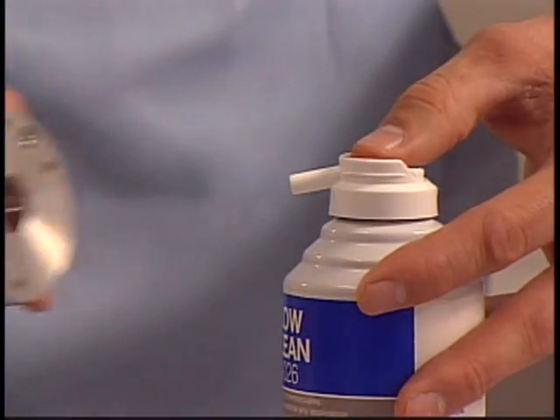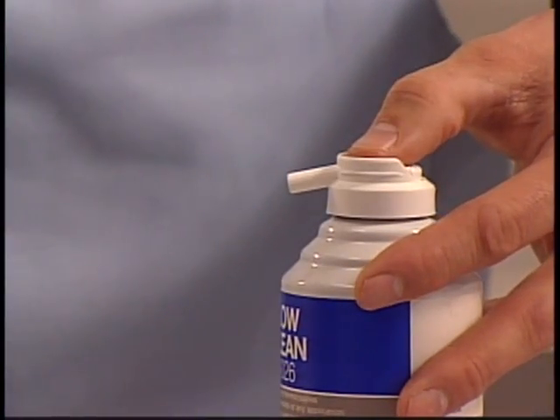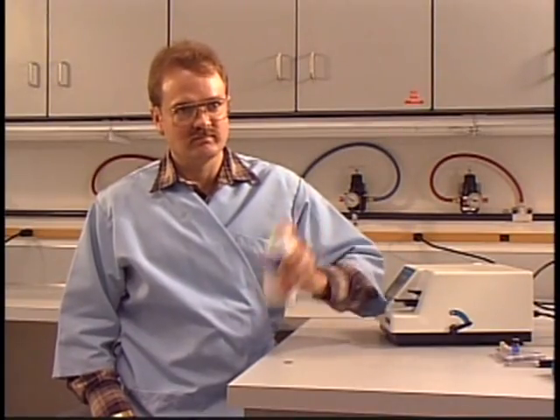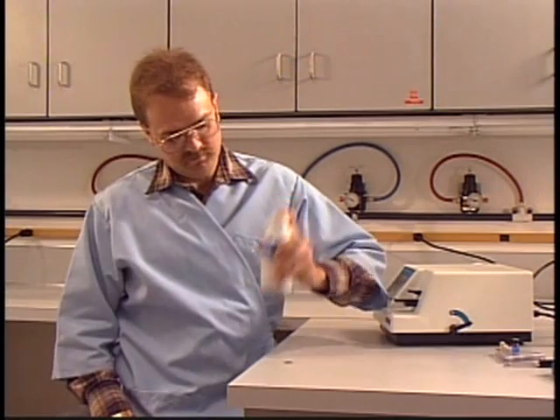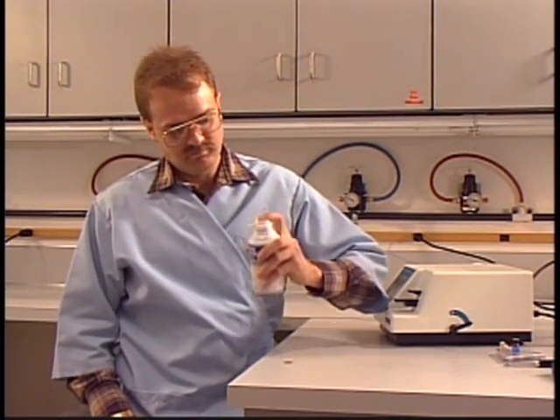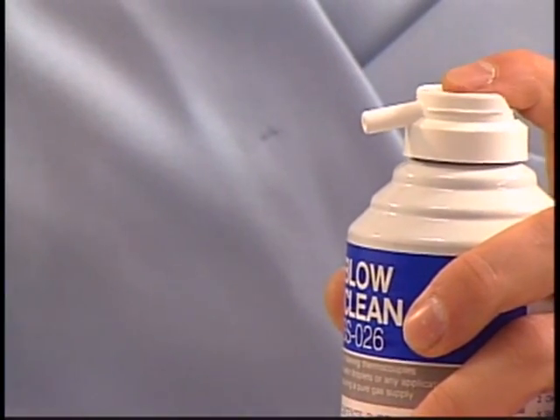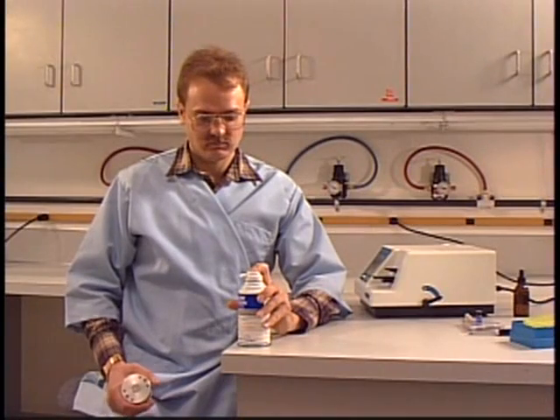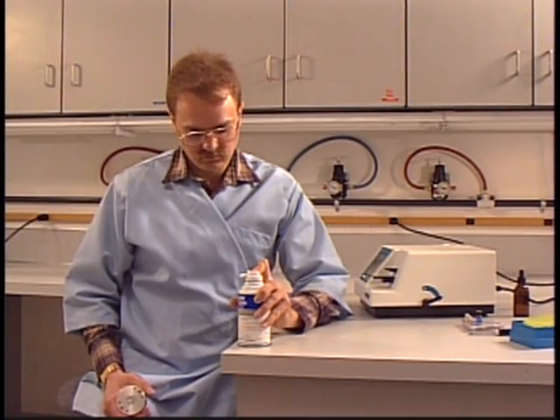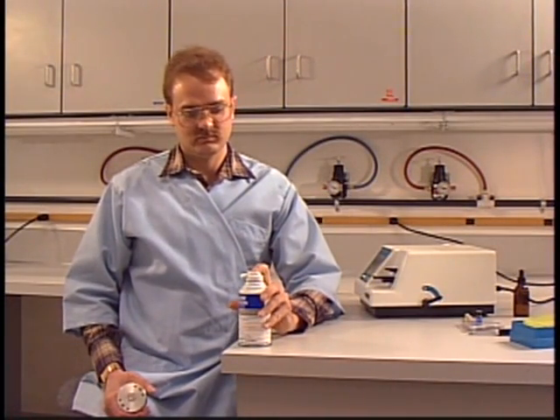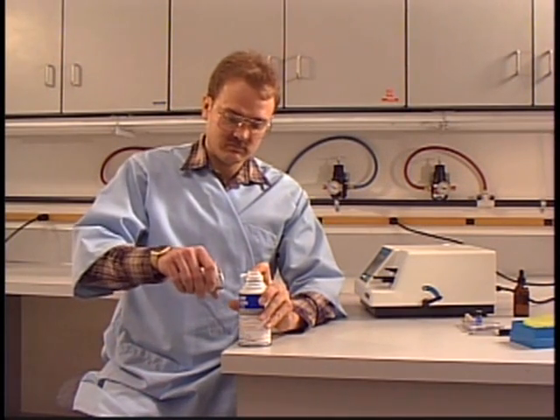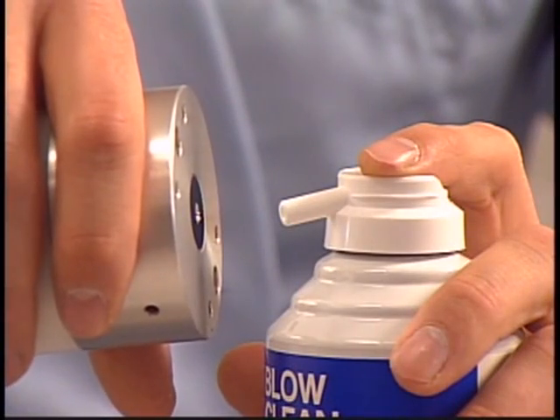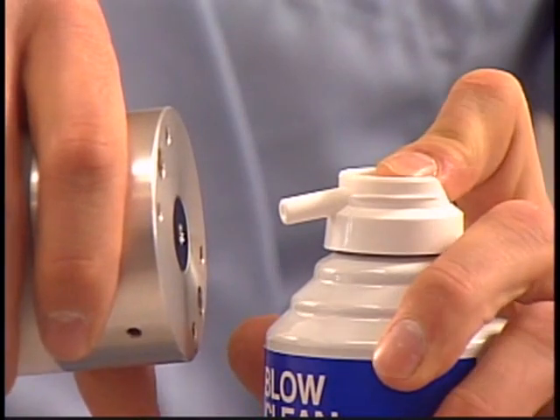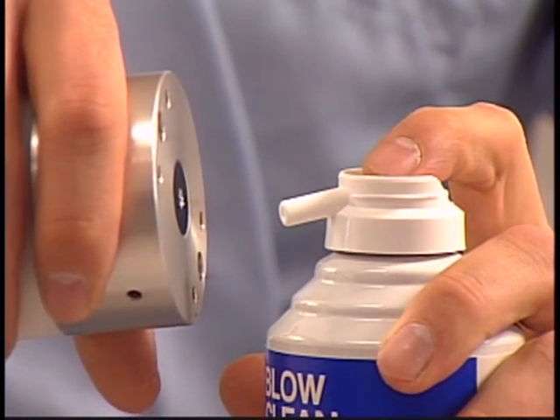Finally, a shot of canned air to speed up the drying process. If you like cleaning osmometers, just shake your air can and blow gunk all over the thermocouple. To avoid that, try another technique. Place your air can firmly on the bench and release a short burst of air to clear the nozzle of compressor oil. Then, without shaking the can, give the thermocouple a 1-second burst of air. A longer blast might cause contamination.